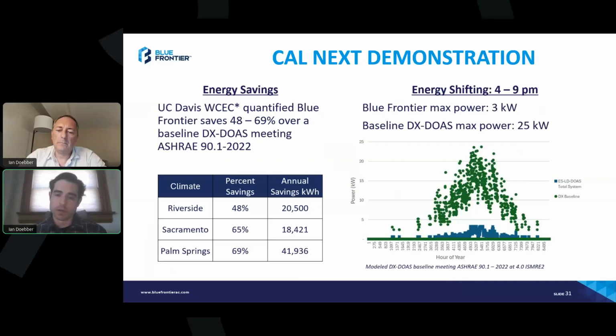During California's peak, our maximum power draw was 3 kilowatts. Again, that's the 3 fans and a small liquid desiccant pump. That was the only thing running, while still providing the full 20-ton cooling capacity of the unit.